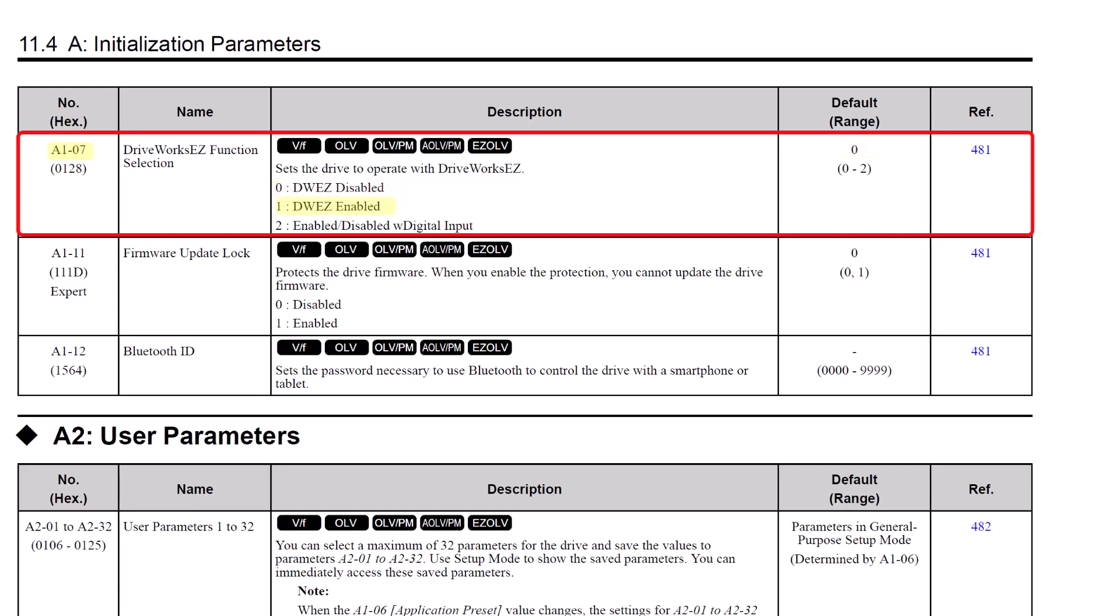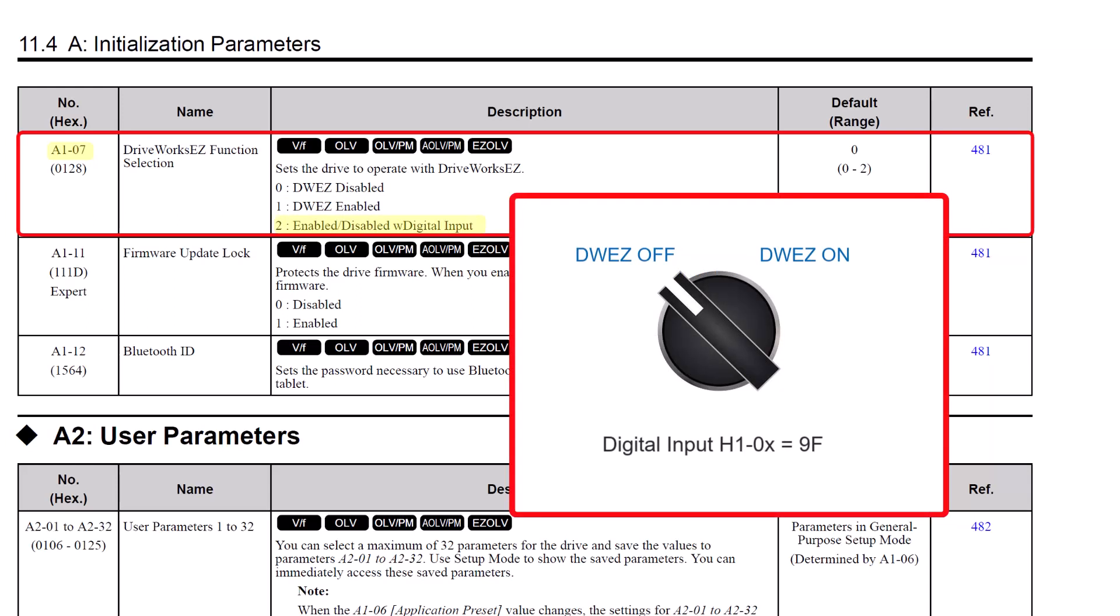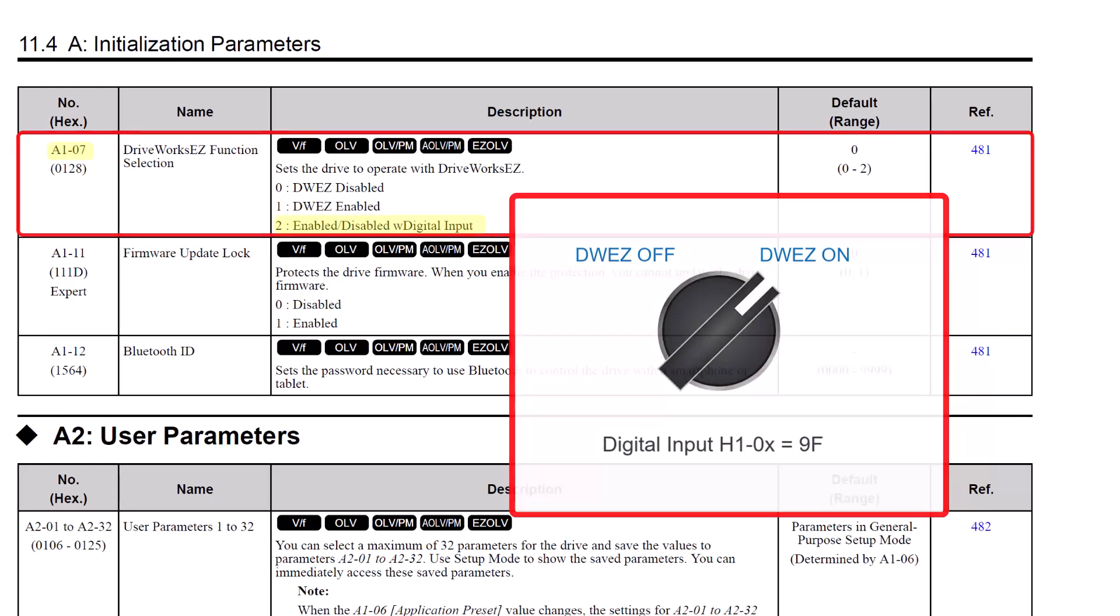You also have the ability to enable DriveWorks EZ on the fly by putting this at a setting of 2 and then programming a digital input of the drive to 9F, which will toggle DriveWorks EZ functionality on and off.